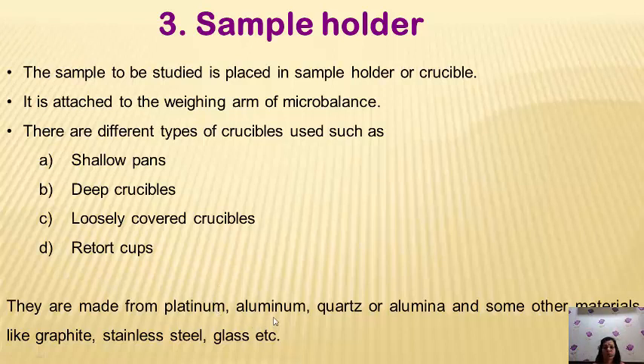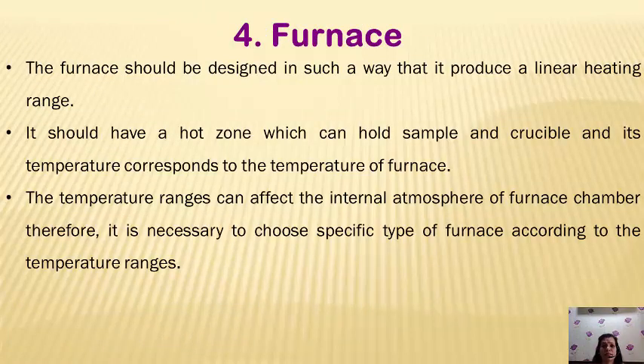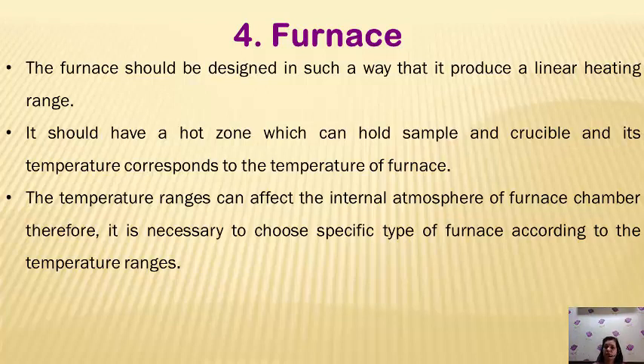Sample holders may be made of platinum, aluminium, quartz, or alumina. Nowadays, graphite, stainless steel, and glass sample holders are also available. The fourth component is the furnace. The furnace is designed to produce a linear heating range. It should have a hot zone which can hold the sample and crucible at the corresponding temperature of the furnace. The temperature range can affect the internal atmosphere of the furnace chamber, so it is necessary to choose a specific type of furnace with the appropriate temperature range.